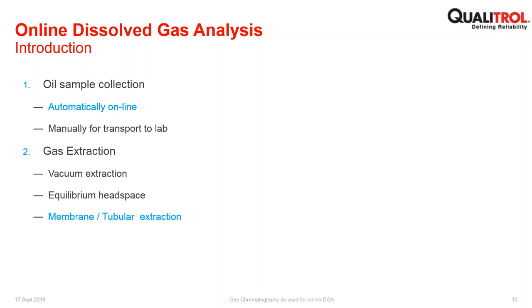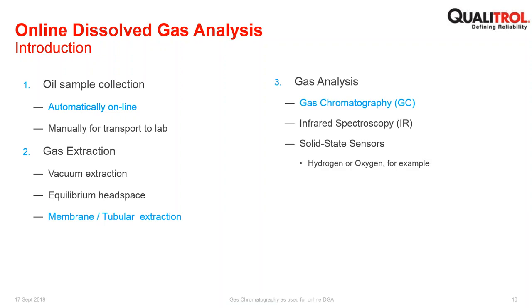You've got to get the gas out of that sample, so gas extraction is the next element. In the laboratory, the traditional method would have been vacuum extraction, not used that much anymore, replaced in a lot of laboratories with equilibrium headspace gas extraction. And indeed, equilibrium headspace is used with some of the online systems. With the Qualitrol system, it's a membrane or tubular extraction, so the use of a semi-permeable membrane to extract the gases out of the oil phase into a gaseous phase.